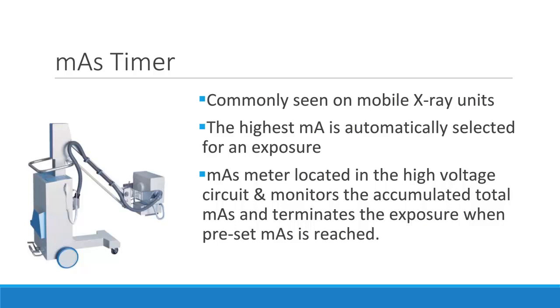This can be an issue when a very long or very short exposure time is desired. For example, a breathing technique is not possible for most mobile units. Additionally, a large body habitus requiring a high MAS would be a challenge on a patient that is moving or is not able to stop breathing with this type of timer.